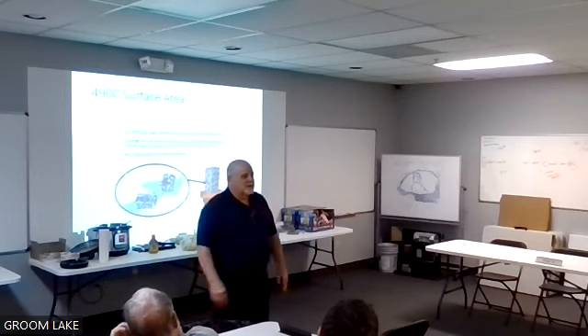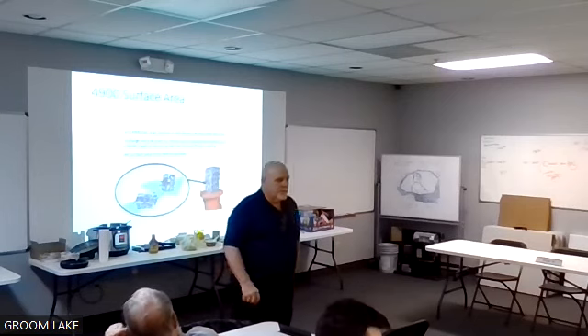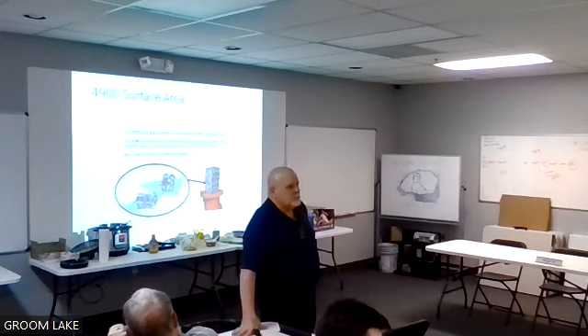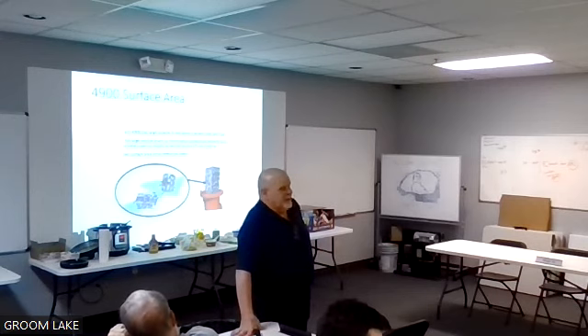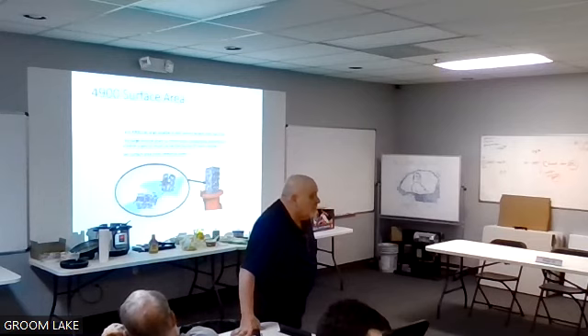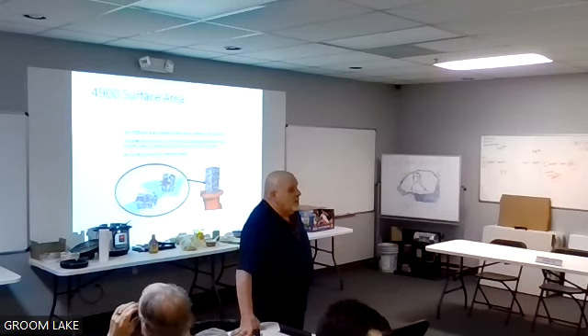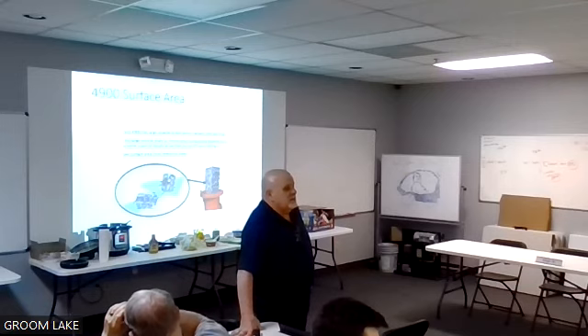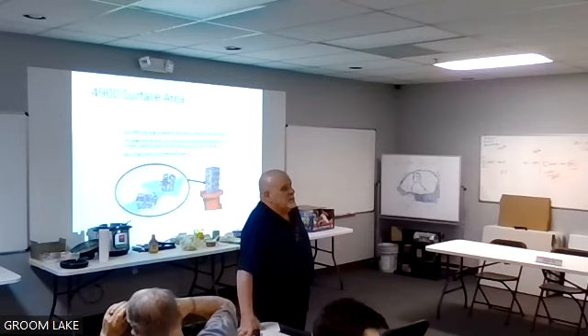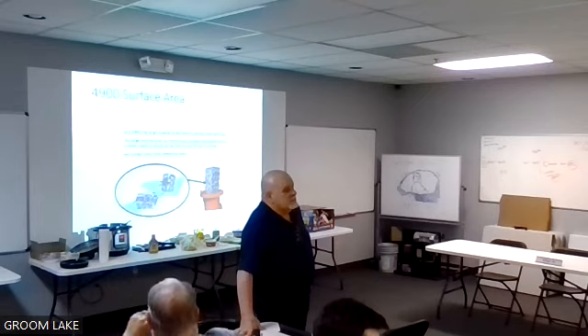That's why the big thing on domestic is, since we got on this subject, above 130, 140 Legionella can't survive. So the higher the temperature, the better when it comes to protecting yourself against Legionella. But the other problem with domestic hot water systems is when you start getting over 160, 165, you have a scald hazard. Well, you could have mixing valves down the line that protect you from that. The problem is in your tank: every bit of minerals and everything is going to precipitate. When you start getting real high temperatures like that, it precipitates all that out.